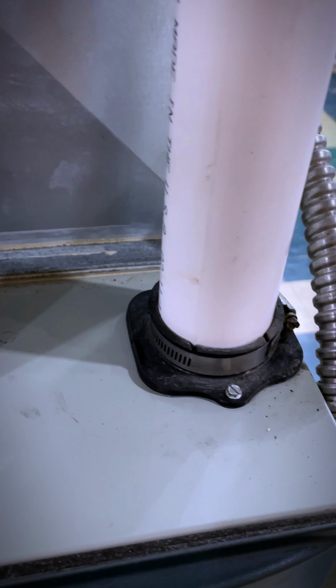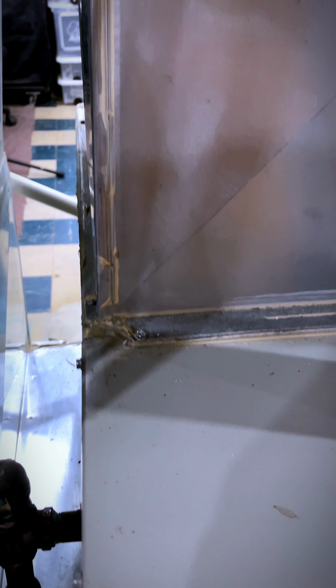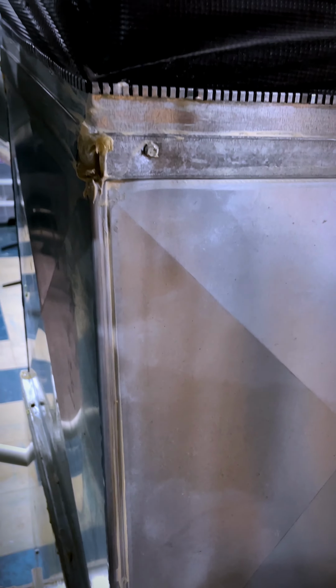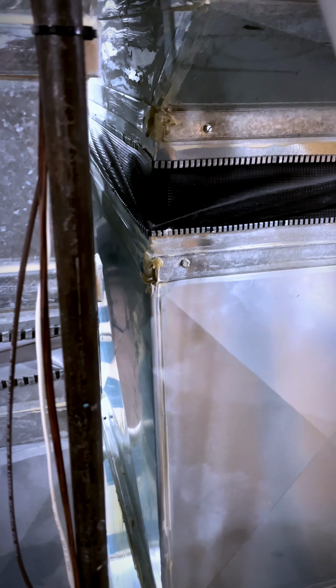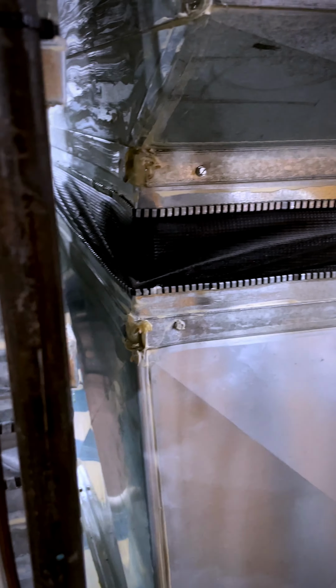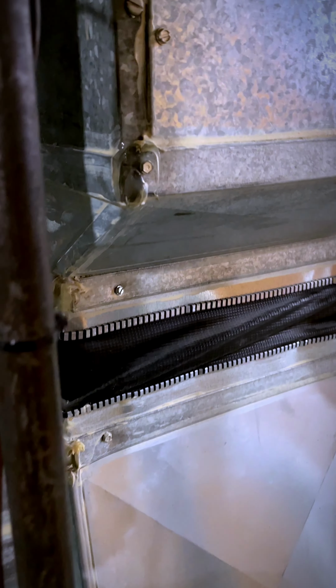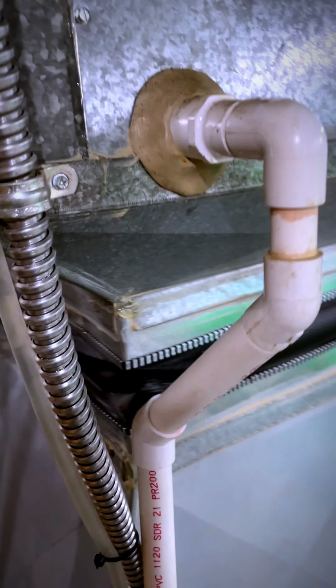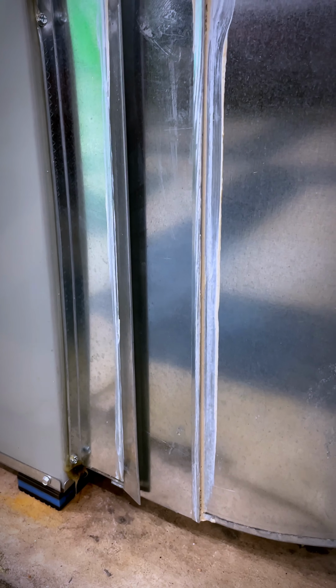I started off by sealing everything up. That means find every seam in all the ductwork and put HVAC sealant. Comes in a caulk tube. Comes in other things too, but I chose a caulk tube because I'm handy with a gun. So I went around and I sealed every single opening on this plenum, on the intake plenum. I sealed up the back door to the filter since we're not using that side.